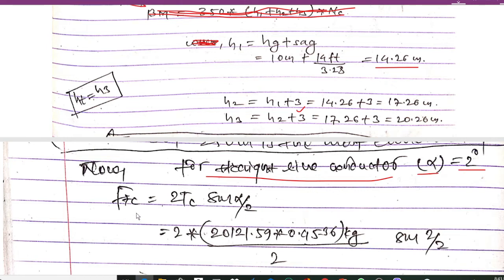The force due to turning of conductor is Ftc = 2 × Tc × sin(alpha / 2). Here Tc = UTS / safety factor. The UTS is 20121.59 pounds; multiplying by 0.4536 converts it to kg, then dividing by the assumed safety factor of 2 gives Tc. With alpha = 2 degrees, sin(1°) is applied. The result is Ftc = 159.29 kg.